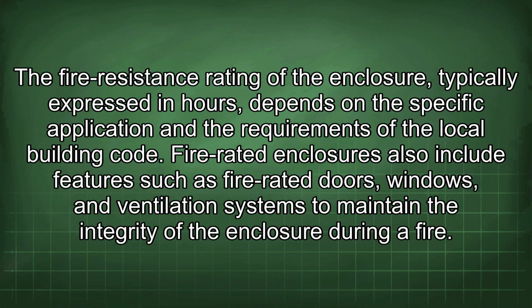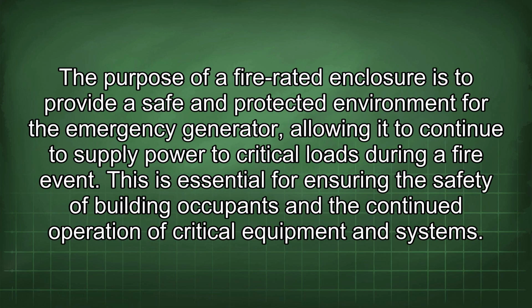The fire resistance rating of the enclosure, typically expressed in hours, depends on the specific application and the requirements of the local building code. Fire-rated enclosures also include features such as fire-rated doors, windows, and ventilation systems to maintain the integrity of the enclosure during a fire. The purpose of a fire-rated enclosure is to provide a safe and protected environment for the emergency generator, allowing it to continue to supply power to critical loads during a fire event. This is essential for ensuring the safety of building occupants and the continued operation of critical equipment and systems.